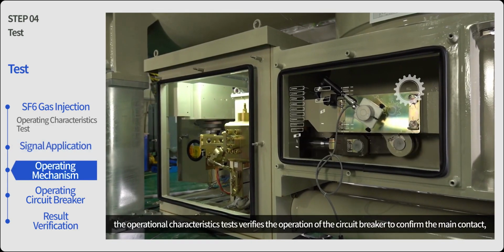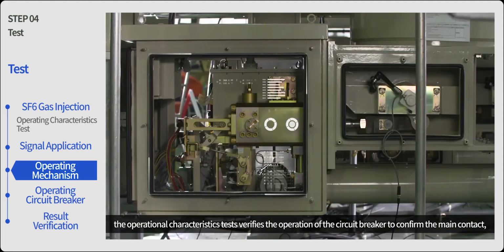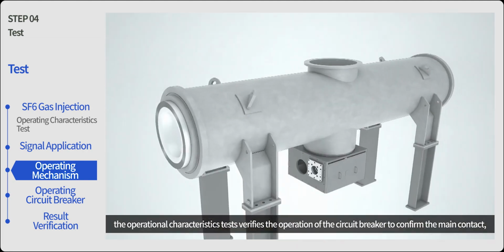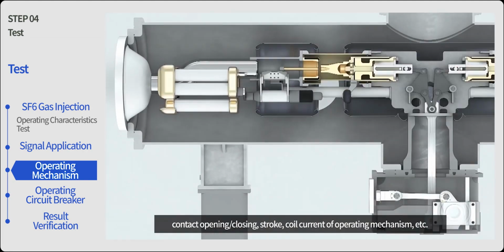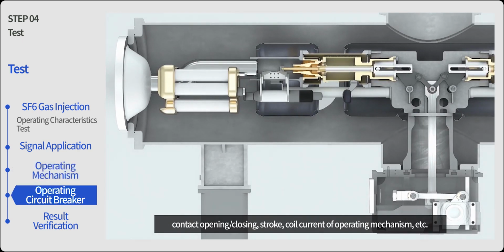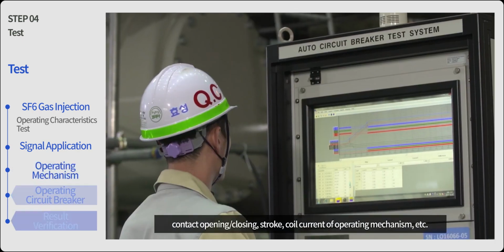Especially, the operational characteristics test verifies the operation of the circuit breaker to confirm the main contact, contact opening, closing, stroke, and coil current of the operating mechanism, etc.